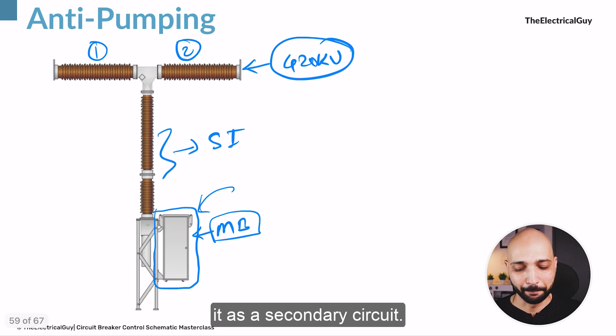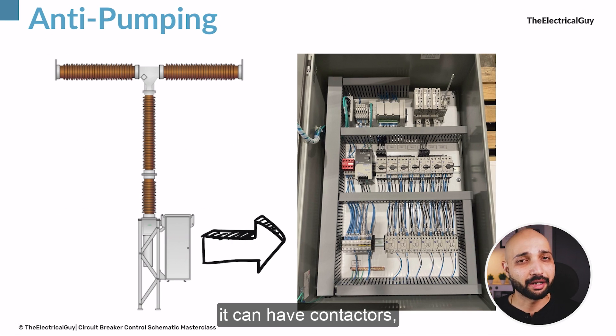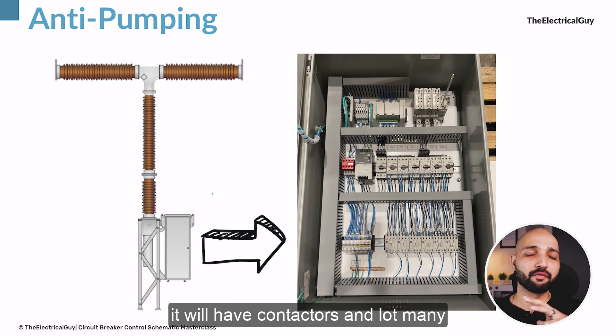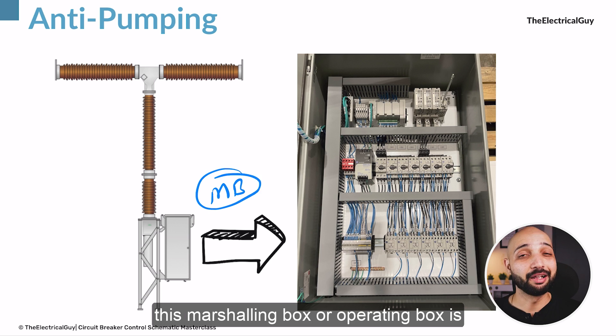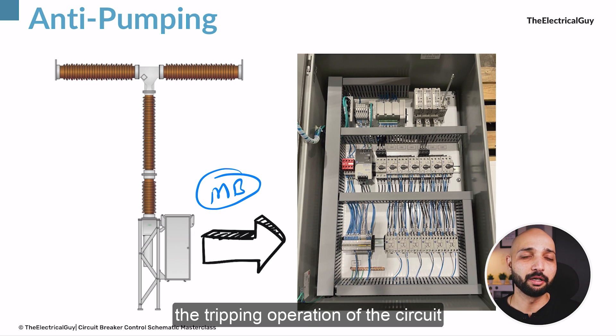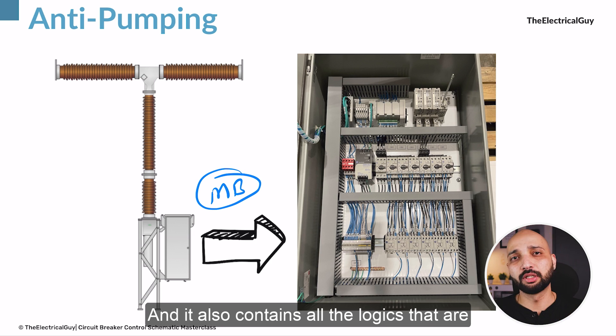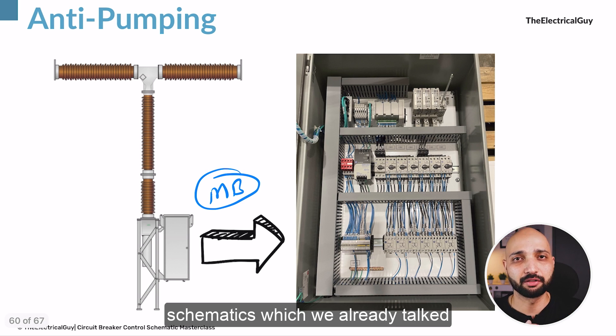What we call the secondary circuit holds a lot of things. For example, it can have contactors, different push buttons, different wiring logics installed into it, and many other things. This marshaling box or operating box is responsible for making sure that the closing operation and the tripping operation of the circuit breaker happen smoothly. It also contains all the logics necessary for the circuit breaker's correct operation — this is what we call control schematics, which we already covered in a previous video.